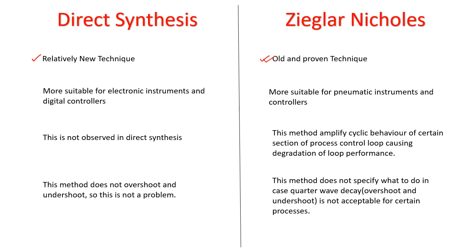But today's valves, controllers, and transmitters are very precise. When the Ziegler-Nichols technique is used on them, the result is often that control loops have a tendency to oscillate. The reason is that today's valves move by the amount the controller output demands. There is very little loss in the transmission of the actuation, so the actuator can move with much less effort.